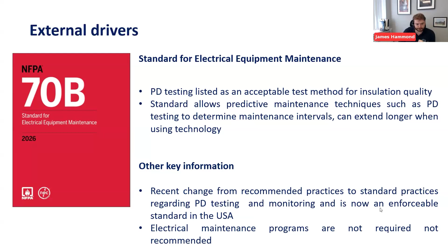To mention a bit more about the NFPA 70B - as you're probably aware, this standard mentions PD quite a few times as one of the permitted tests for high voltage and lower voltage assets, and it's now a mandatory standard. It's important that this, or some type of insulation testing, is being carried out.